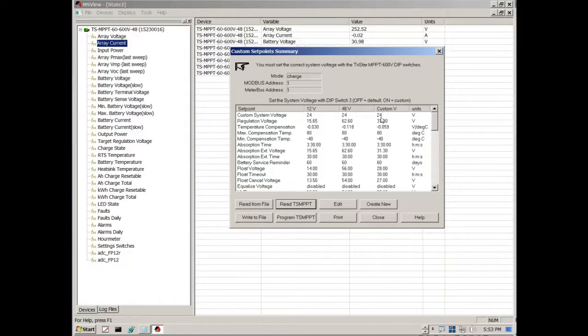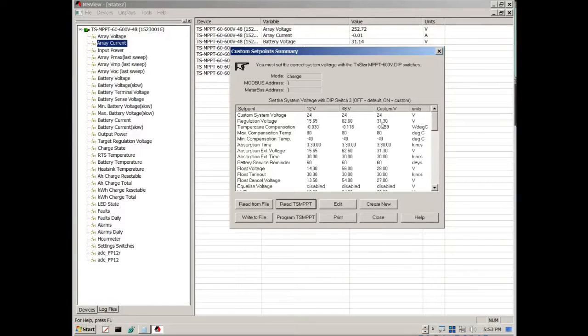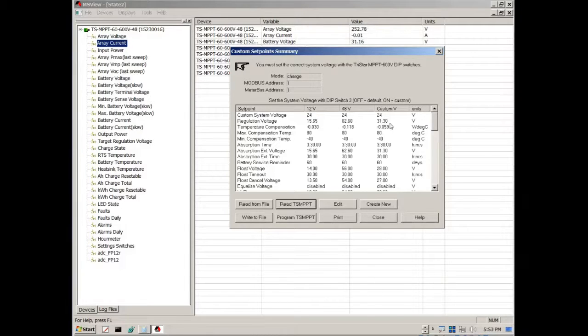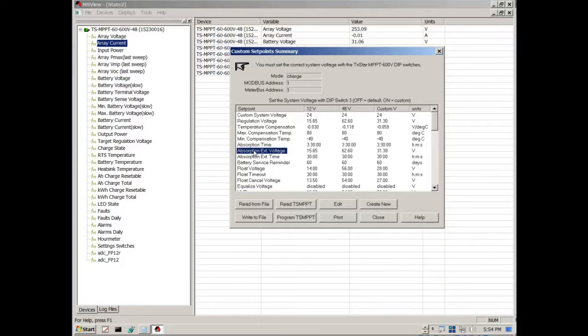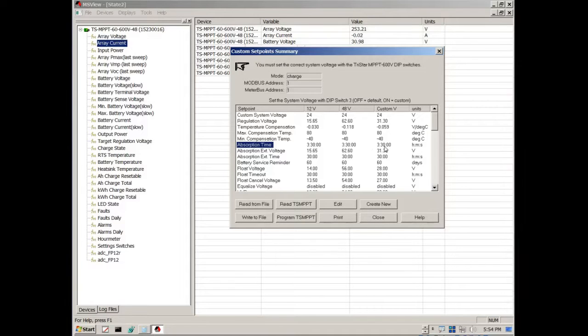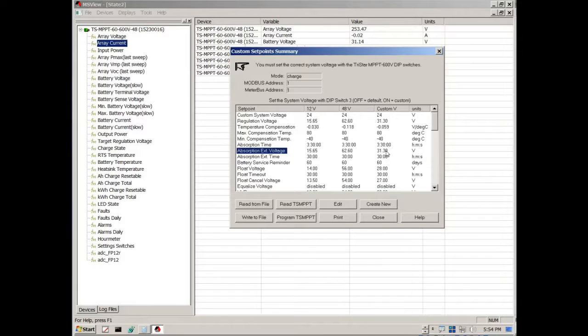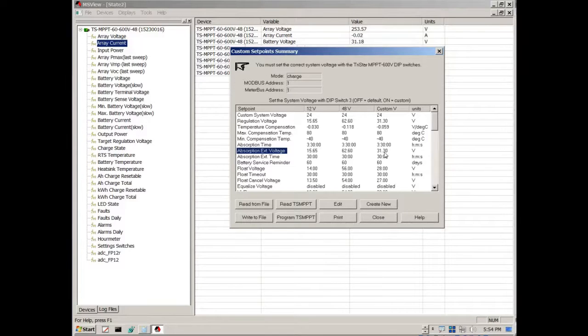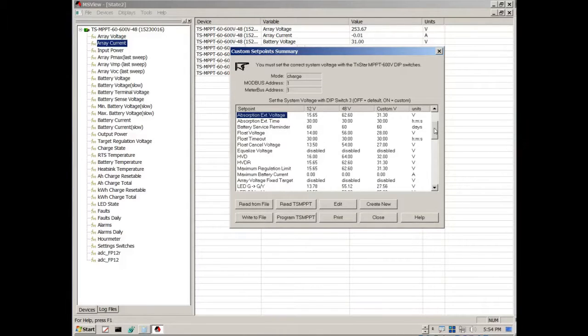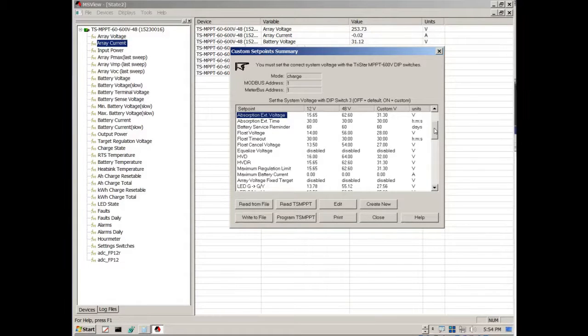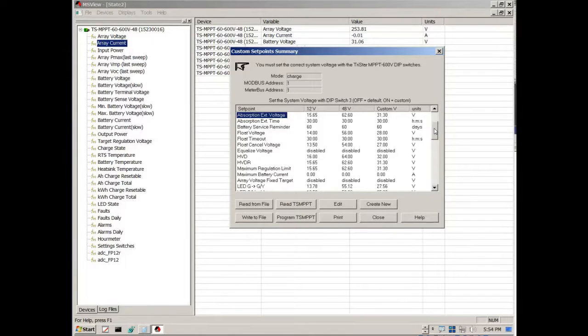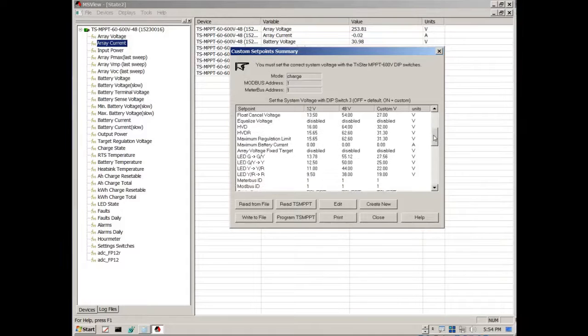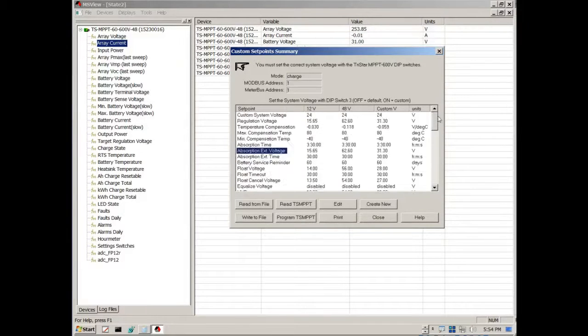Like for instance it's a custom setting, it's 24 volts not 48. And the regulation voltage. I'd say I want regulation, I don't want it to get higher than 31.30. That's what I'm shooting for. Like for instance also the absorption time. I want it to charge for 3 hours and 30 minutes. And the absorption voltage which comes after the bulk stage. So I just say I want it 31.3 volts. And you can see all of these parameters here. The float voltage, the absorption voltage, the absorption time. If there is an extension time to the absorption. All of these things can be programmed with this particular unit.